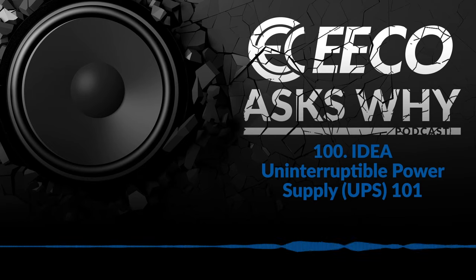That's something I've run across before, where users will say, hey, I just bought this fancy new UPS and it's not working for me. We dive deeper into it and find out, well, you're only rated for 1,000 VA, but you've got 1,800 VA worth of stuff plugged into it. That's why it's not providing that battery backup. So you definitely need to keep in mind the amount of items you have plugged in and that power consumption.